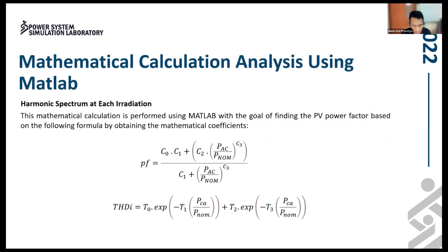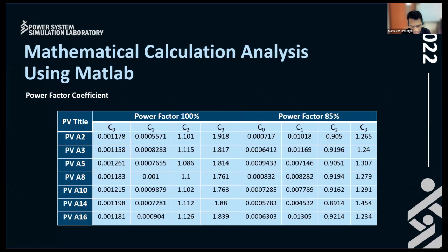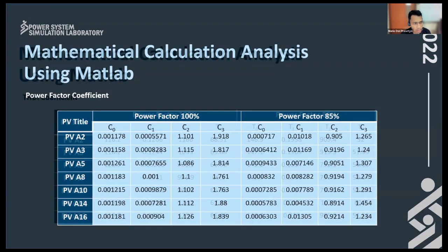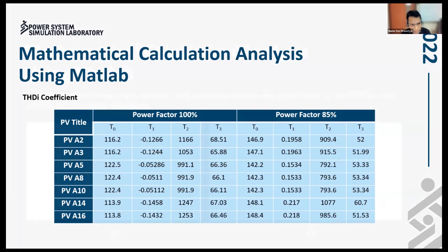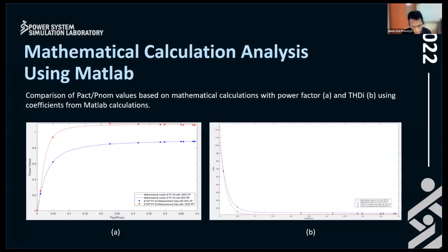And then we calculate the result from ETAP analysis using power factor and current THD equations. From these equations, we have a power factor and current THD coefficient that represent the inverter system character for 100% and 85%. It is the power factor coefficient, and it is the current THD coefficient. So for the calculation, we get the comparison between ETAP simulation and mathematical calculation for the power factor and current THD curve. From the figure, we also know that the curves between ETAP and mathematical calculation are similar. That means ETAP and the mathematical model can be used for planning the PV system for analysis of generation and current THD.